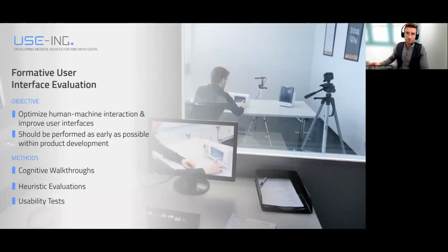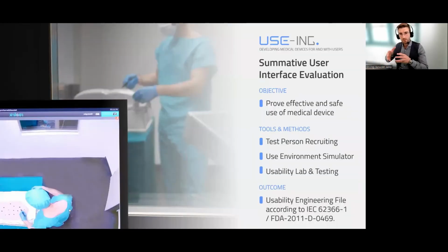So just to give you a short insight, how can those evaluations look? They are usually performed in usability labs. They are filmed, representative medical users are recruited, and then different methods are used, like cognitive walkthroughs, heuristics, or usability tests. Key on the summative in comparison to the formative user evaluation is, as mentioned before, to prove the effective and safe use of the medical device.